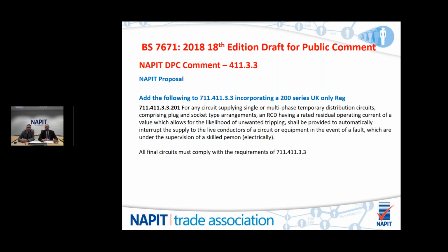So, again, a comment followed by a proposal. NAPIT are proposing to add the following to 711.411.3.3, which will incorporate a new 200 series UK-only reg. If you like, this will allow a temporary distribution circuit, a pre-tested extension lead, for distribution circuits only. That will go from source to a site board or some other kind of arrangement. And from that point on, socket outlet circuits or final circuits will comply with the requirements of 711.411.3.3 and particular RCD requirements.